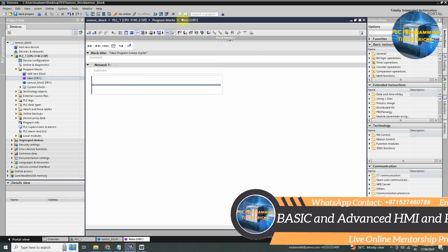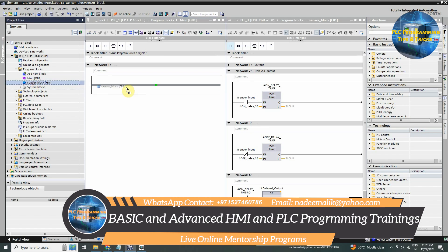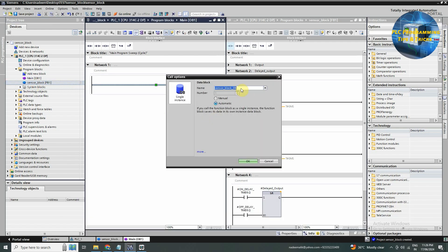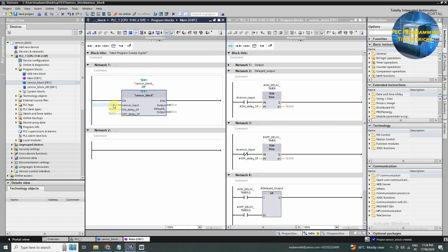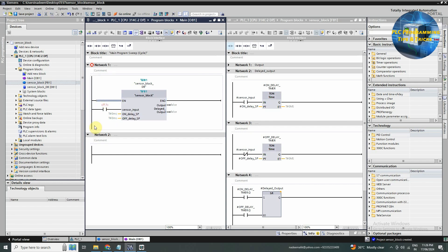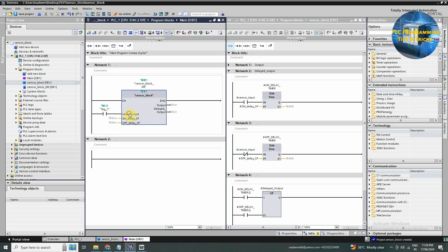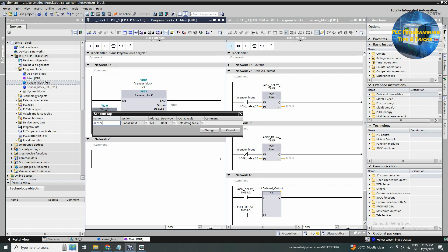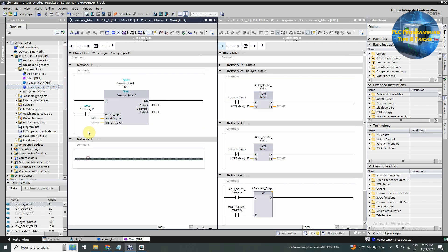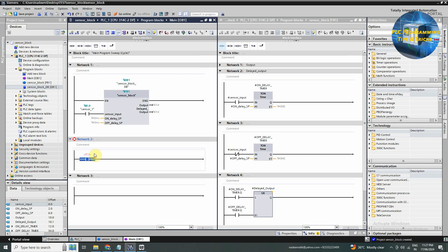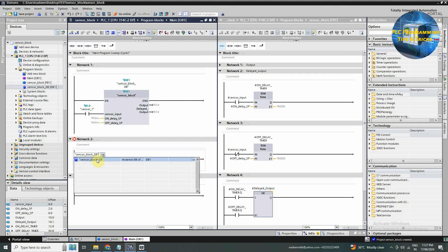We will open OB1 and drag and drop this function block. This will create an instance of this block; we can give it any name. We will drag and drop a normal open contact at the sensor input of this instance and assign the PLC input I0.0. Our actual sensor is connected at the I0.0 input of the PLC. Next we will drag and drop a normal open contact in network two, copy the name of the DB for this function block instance and paste this name on this normal open contact.